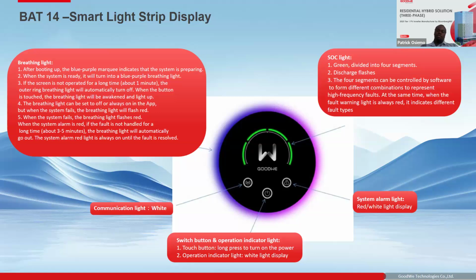And yeah, we also have the SOC strip light that fills up in accordance to the charge level of the battery. We also do have the communication LED to show you whether the battery is achieving communication or not. We have an alarm system, which either goes red or white to show you the status, whether we have an alarm or not. We also have a button to switch on, and it also has a color to show you whether it's already switched on or not. So this combination gives you a very, let me say, snapshot of the operating condition of the BAT14. So just by seeing the glow of the LEDs, you will be able to understand what's happening with your BAT14 series.